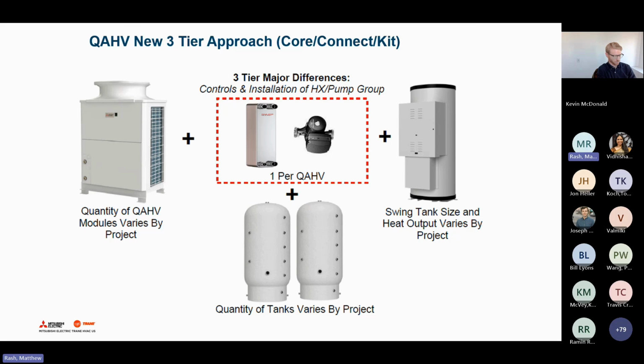Again, just to recap, the QAHV product is a CO2-based heat pump hot water heater, strictly for domestic hot water. It's geared for extremely high delta T type applications like domestic water, not for low delta T heating hot water, building HVAC type applications. That's where the CAHV product is going to fall, and we'll go through that in a little bit more detail. So again, it's CO2 based, with a fairly high COP depending on conditions, obviously removing ozone depletion potential, with very low GWP, and hot water temperatures at the highest level that we offer across any of our lineup, up to 176 degrees.